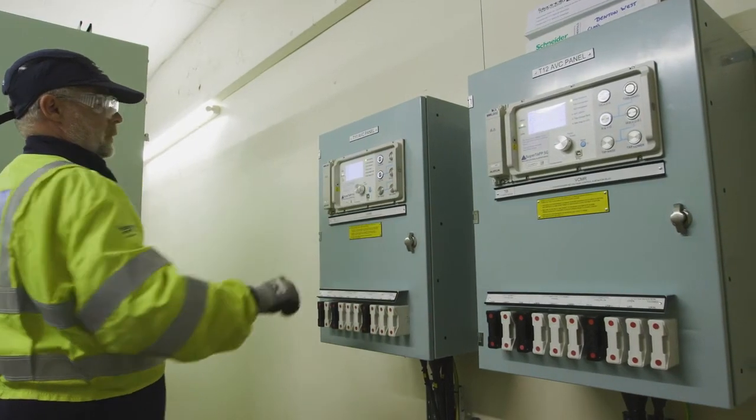So we then set our volumes, the prices for what's called availability, which is the price that we'll get just to be available for National Grid, and then the price for utilisation, which is the price that we get if National Grid then choose to activate us. We then get that price. So we submit these prices on a daily basis, and then we have a look at how often we're monitored or used to see whether or not we should adjust those prices.